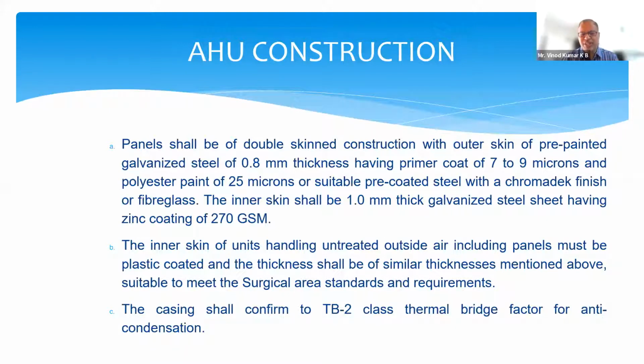See, corrosion inside the AHU can never be seen. If you look at an AHU, the moment it is switched on, it is going to run forever. You will never be switching off the AHU. Nobody will go into the AHU to see this. Hence, it's important to make sure that you select the AHU with the correct kind of skin. The inner skin should have a coating. This 270 grams per square meter of zinc coating will not allow corrosion to happen. That is a prime factor about this.